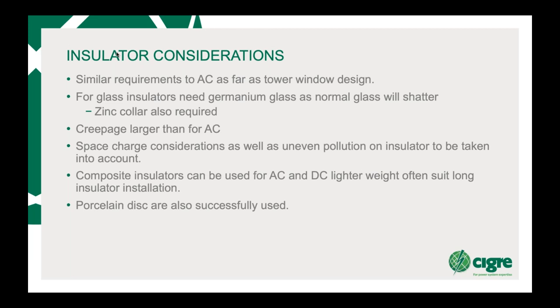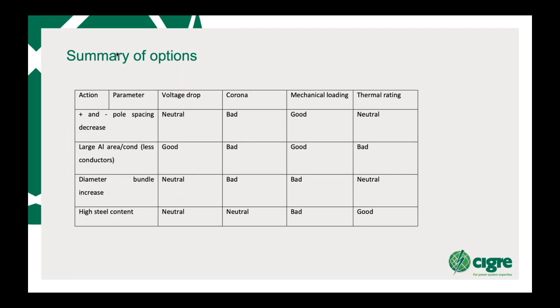Just looking then at the summary of options, if you decrease your pole spacing, it's bad for corona, but again, good for mechanical loading. This is on a bipolar line. Volt drop and thermal rating are about the same. If you're looking at a large aluminium area, it's good for volt drop, bad for corona, good for mechanical loading, and bad for thermal rating, as again, for the same reasons mentioned for AC.